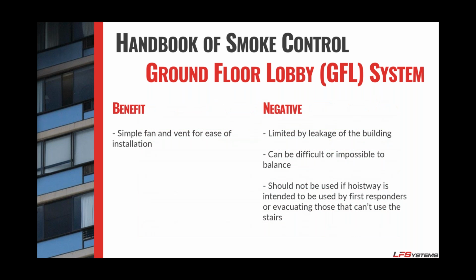So again, it's a very simple fan and vent layout. It can save some costs, but it's limited by your leakage in the building. It can be very difficult to, impossible, that's ASHRAE's words, not mine. Difficult or impossible to balance. And it definitely should not be used if you intend to use your elevator hoistways for first responders or for evacuating those that can't use the stairs.